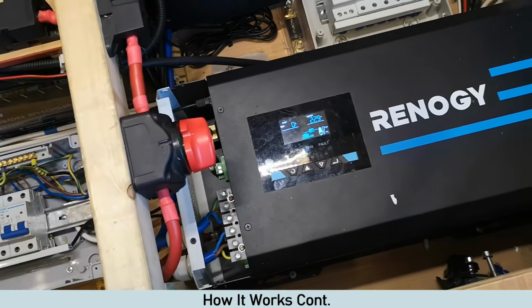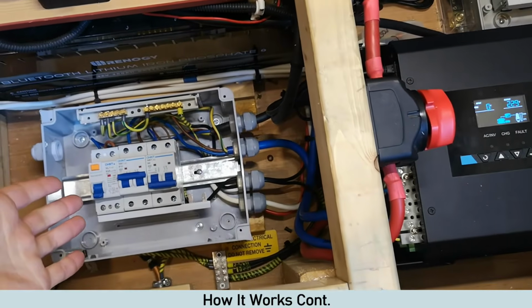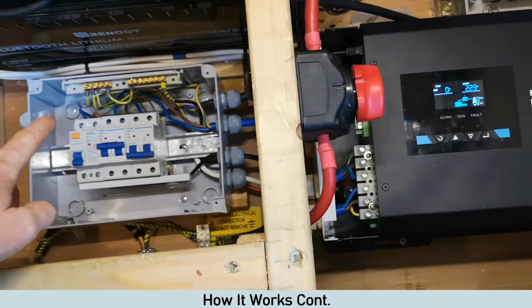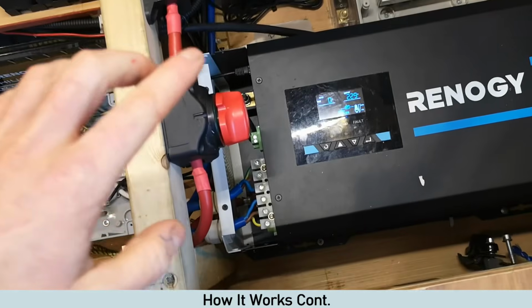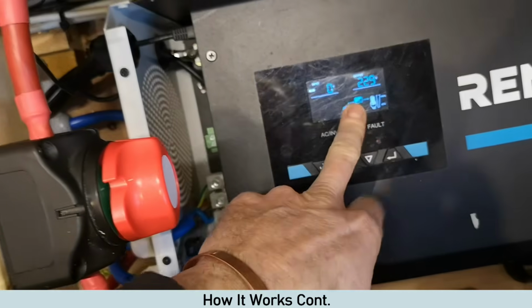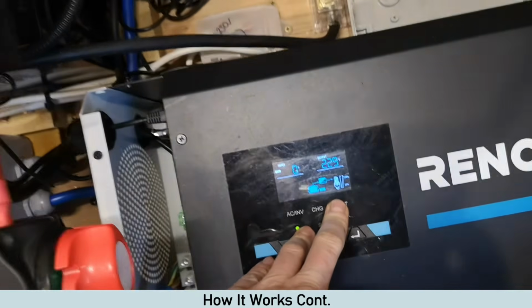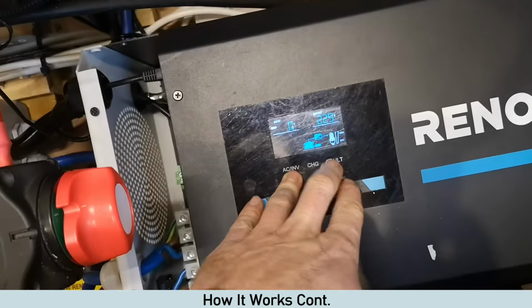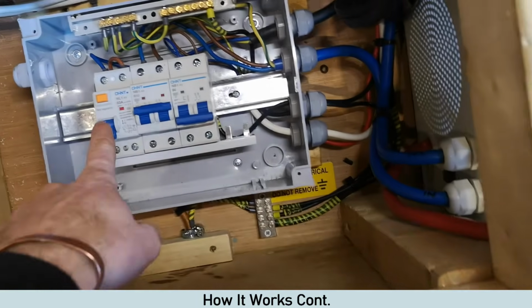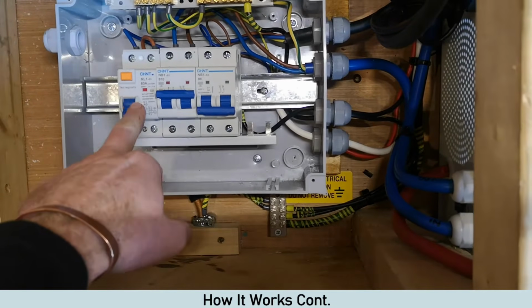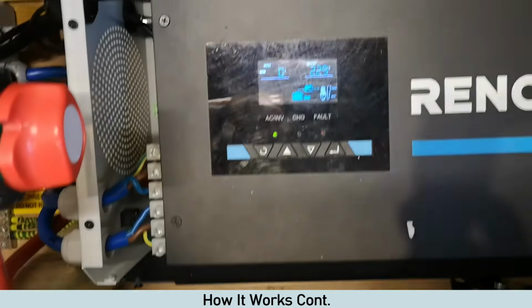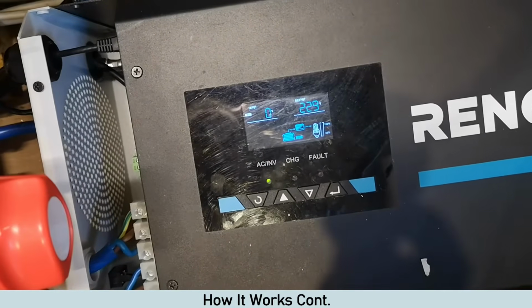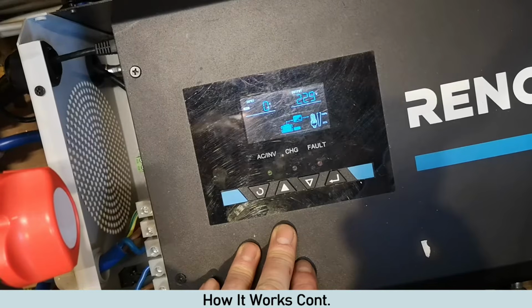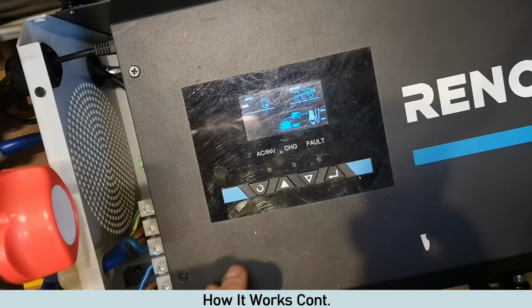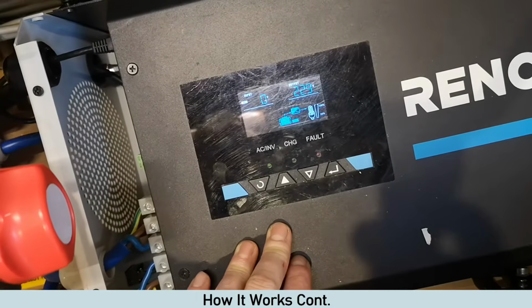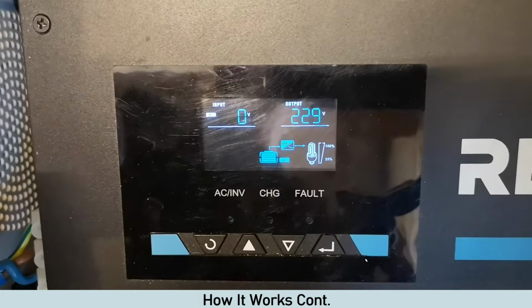The next thing I'll show you is what happens when power comes back on here. So before we do any testing with the RCD tester, I'll just switch that on and show you what happens. Currently it's on, obviously, inverter, fan's on, hopefully it's not disturbing me too much. The system is centre tapped, so it's powering our loads. Power's off here. Now I'm going to turn this on, but this doesn't switch over immediately. It takes about 8 seconds, and I think that is so it's looking at the voltage. When it sees power come in, it's going to sit and make sure that voltage is stable before it switches. I'll position you there, switch it on and show you what happens.